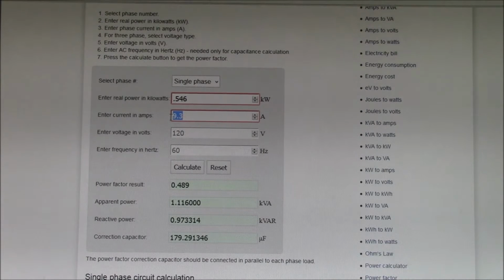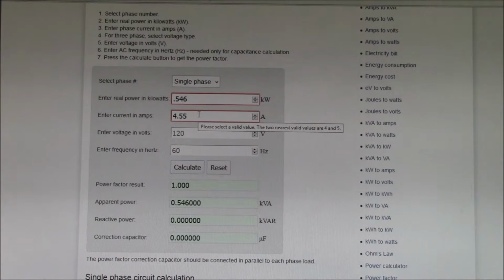And then just as a data point from the video, I plugged in a capacitor and it dropped my current to 8.05 amps. And you can see down here the correction capacitor is now about 150 microfarads. It was 180. The difference is 30, and that happens to be the size of capacitor I plugged in. The other data point here is the kilowatt meter was, I think, measuring 970 volt amps, and this calculator is saying 966 with that capacitor plugged in, so that lines up as well. If we were to fully correct the power factor of that washing machine motor, I just happen to know that 4.55 amps brings the power factor to unity, and my current I've dropped from 9.3 amps down to 4.55 amps, better than a 50% reduction just by plugging in a capacitor.